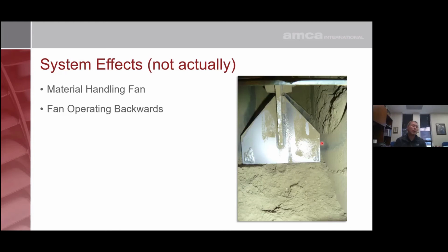In this case, this is a fan that was used on a dust collector system. The fan was able to move enough air to pick up dust at the source, but it wasn't moving enough air to keep that particulate entrained in the gas stream while the fan was in operation. So all that dust dropped out of the ductwork and into the fan, and it creates a huge housekeeping issue, a huge safety issue. That ductwork was never designed to support that kind of mass load. Consequently, they're at risk of that ductwork collapsing in the middle of the facility. So safety-wise, it's very important to make sure the fan's rotating in the proper direction.